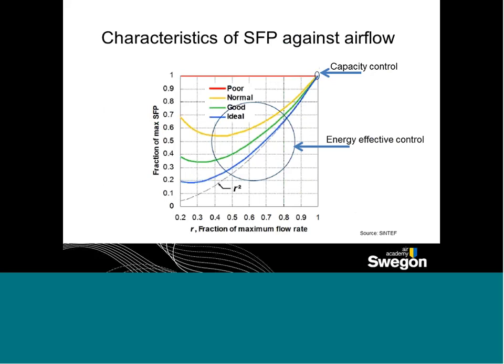If we look at the characteristics of specific fan power against airflow, the red line at the top characterizes a constant air volume system. As we go through yellow, green, and then towards the blue line, you see the different degrees of how you're controlling the system, with the optimal being towards the lower blue line. That's where you have the most ability to save energy while still getting the maximum benefit.